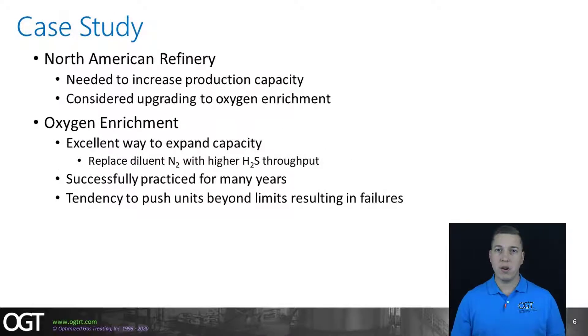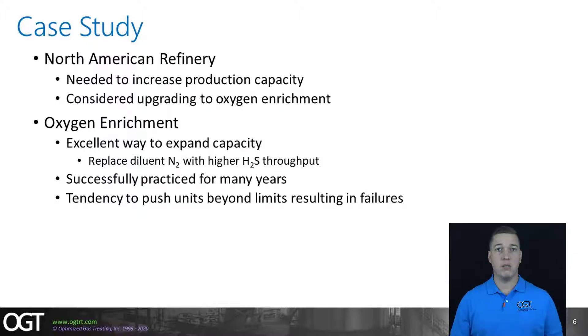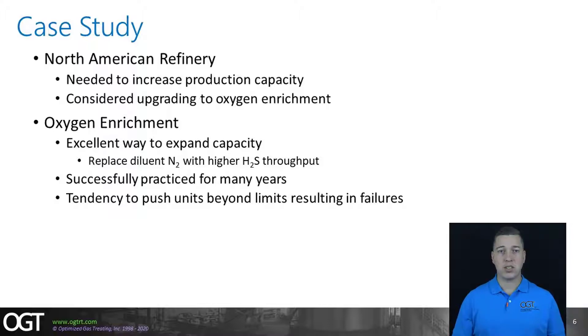The case involves a North American refinery that was considering adding oxygen enrichment to their Claus unit in an effort to increase production capacity. Oxygen enrichment in an SRU can be a simple and inexpensive way to squeeze more hydraulic capacity through a plant without requiring a huge capital expenditure — it increases the oxygen content in combustion air, reducing the nitrogen content, allowing the capacity taken up by nitrogen to be used by H2S in the feed gas. This type of capacity expansion has been practiced successfully for many years, oftentimes without incident. However, if the plant is already dangling on the edge, adding in oxygen can be the straw that causes it to fail, sometimes catastrophically.